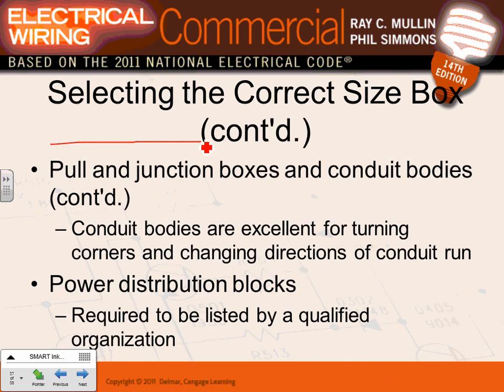Pull boxes: you use a pull box when pulling a long feeder - say 100 to 400 feet - between two buildings, putting a pull box in between to make pulling conductors easier. Also, if you have more than 360 degrees of bends in a conduit run, you must have a pull box. What makes a box a pull box? If you bring at least one conductor number four or larger into any box, that box changes from a junction box or device box into a pull box, and certain calculations are required to size it.